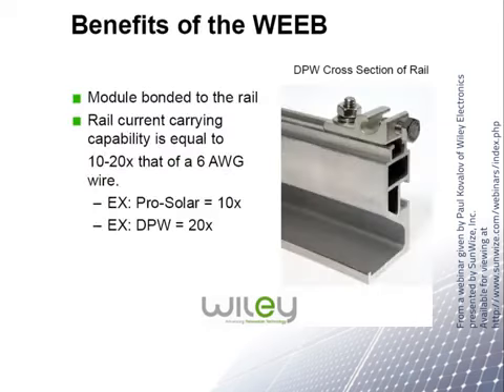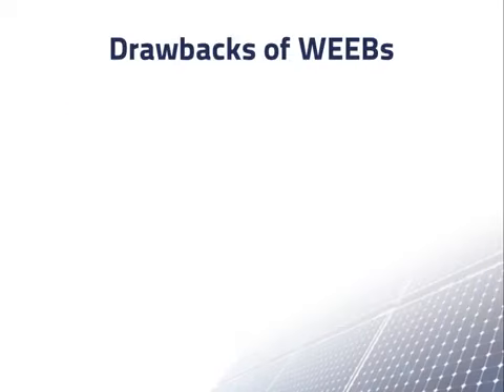Here is the statement that rails by different manufacturers actually have 10 to 20 times the conductivity of the 6 AWG copper grounding wire commonly used for conventional grounding. The conductivity is different for the rails made by manufacturers ProSolar and DPW. But of course, there are also disadvantages of WEEB connectors, which do not appear in the manufacturer's information.